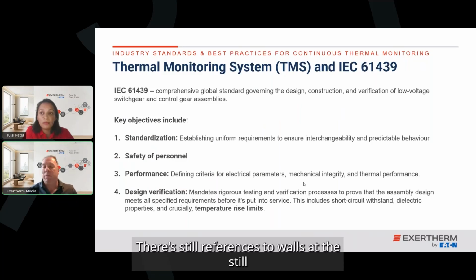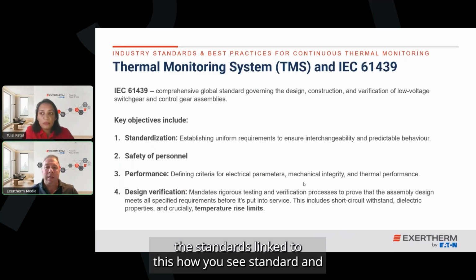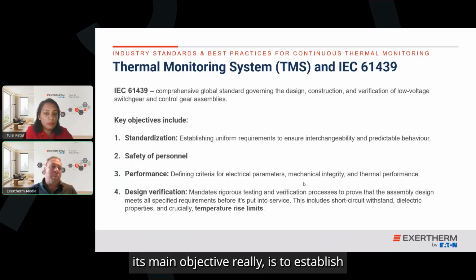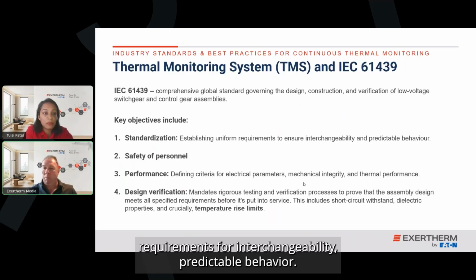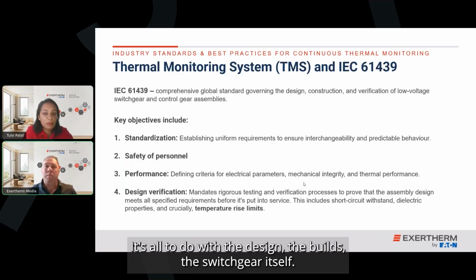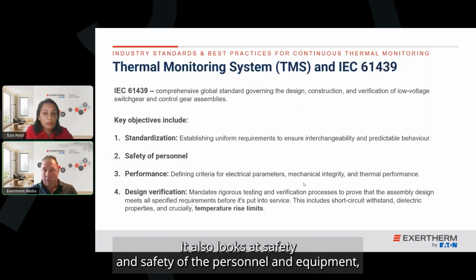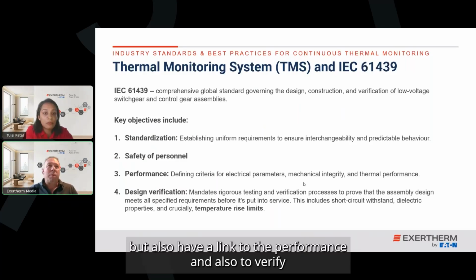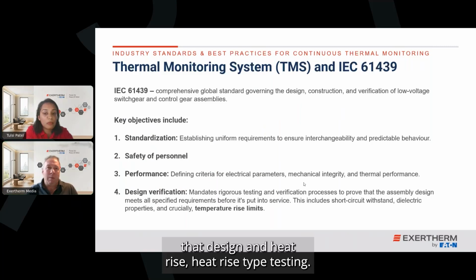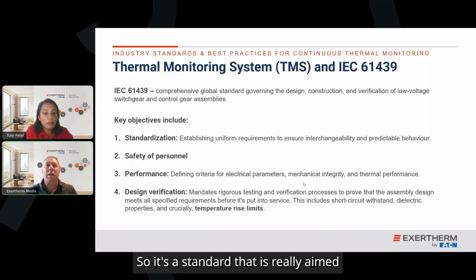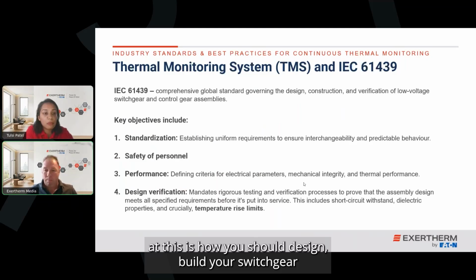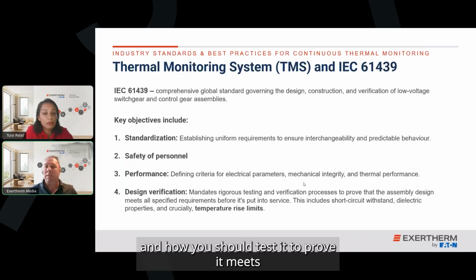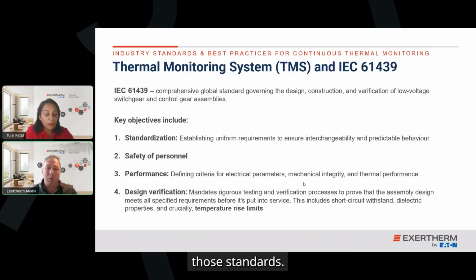There are still references towards it. There's still other standards linked to this IEC standard, and its main objective really is to establish requirements for interchangeability, predictable behavior. It's all to do with the design and the build of the switchgear itself. It also looks at safety of the personnel and equipment, but also heavily into the performance and also to verify that design in heat rise type testing. So it's a standard that is really aimed at this: this is how you should design and build your switchgear and how you should test it to prove it meets those standards.